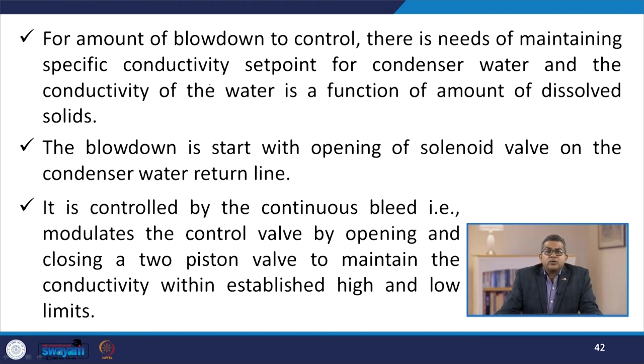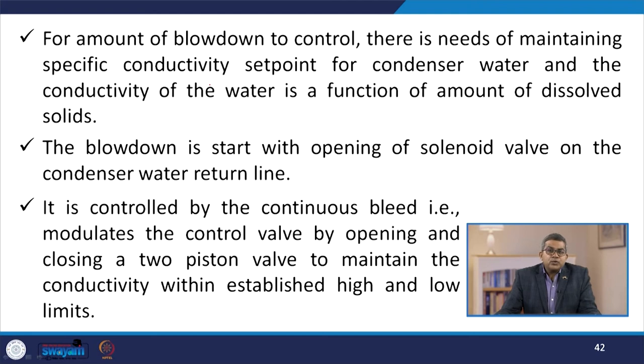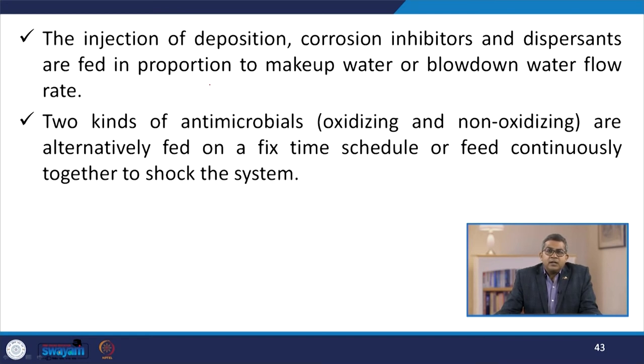For blowdown control, there is a need to maintain a specific conductivity set point for condenser water. Conductivity of the water is a function of the amount of dissolved solids. Blowdown starts with the opening of a solenoid valve on the condenser water return line, controlled by continuous bleed that modulates a control valve by opening and closing a two-position valve to maintain conductivity within established high and low limits. Deposition and corrosion inhibitors and dispersants are fed in proportion to makeup or blowdown water flow rate. Two kinds of antimicrobials — oxidizing and non-oxidizing — are alternatively fed on a fixed time schedule or fed continuously together to shock the system.